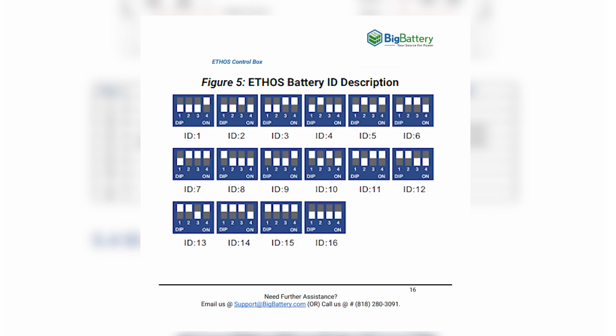I will start with the battery closest to the controller box and give it ID 1: down, down, down, up. The next battery below that will get ID 2: down, down, up, down. Then the bottom one will get ID 3: down, down, up, up. Starting at the top of our next stack, ID 4: down, up, down, down. Then ID 5: down, up, down, up. And the last one will be ID 6: down, up, up, down.